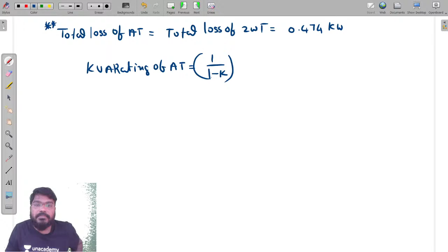So that's why here, but kVA rating is different. Now the kVA rating of the auto transformer is equal to 1 by 1 minus k times the kVA rating of the two winding transformer. So now this value is equal to 1 by 1 minus k, where k is low voltage by high voltage. So now how do we calculate this k value? That is 240 divided by 360 volts. Okay, k of auto transformer.